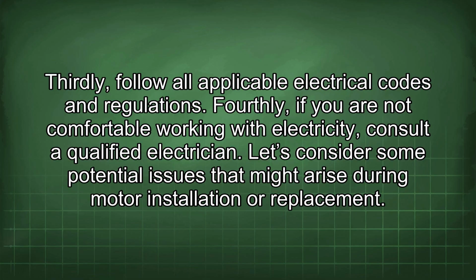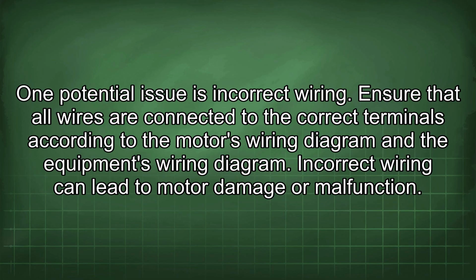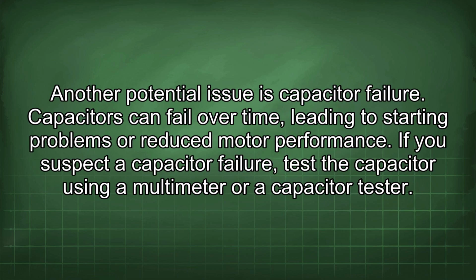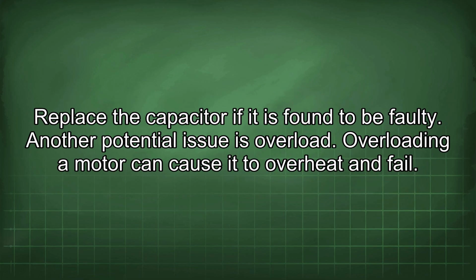Let's consider some potential issues that might arise during motor installation or replacement. One potential issue is incorrect wiring. Ensure that all wires are connected to the correct terminals according to the motor's wiring diagram and the equipment's wiring diagram. Incorrect wiring can lead to motor damage or malfunction. Another potential issue is capacitor failure. Capacitors can fail over time, leading to starting problems or reduced motor performance. If you suspect a capacitor failure, test the capacitor using a multimeter or a capacitor tester. Replace the capacitor if it is found to be faulty.